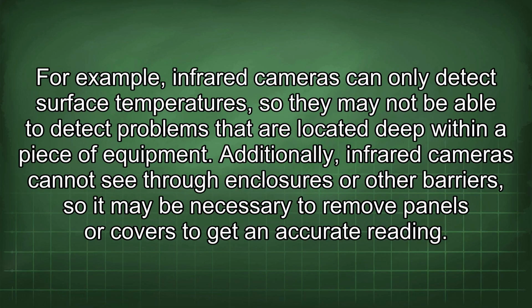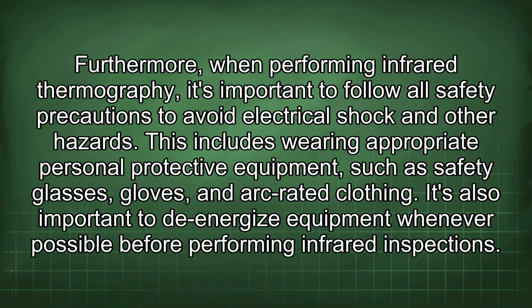For example, infrared cameras can only detect surface temperatures, so they may not be able to detect problems that are located deep within a piece of equipment. Additionally, infrared cameras cannot see through enclosures or other barriers, so it may be necessary to remove panels or covers to get an accurate reading. Furthermore, when performing infrared thermography, it's important to follow all safety precautions to avoid electrical shock and other hazards. This includes wearing appropriate personal protective equipment, such as safety glasses, gloves, and arc-rated clothing. It's also important to de-energize equipment whenever possible before performing infrared inspections.